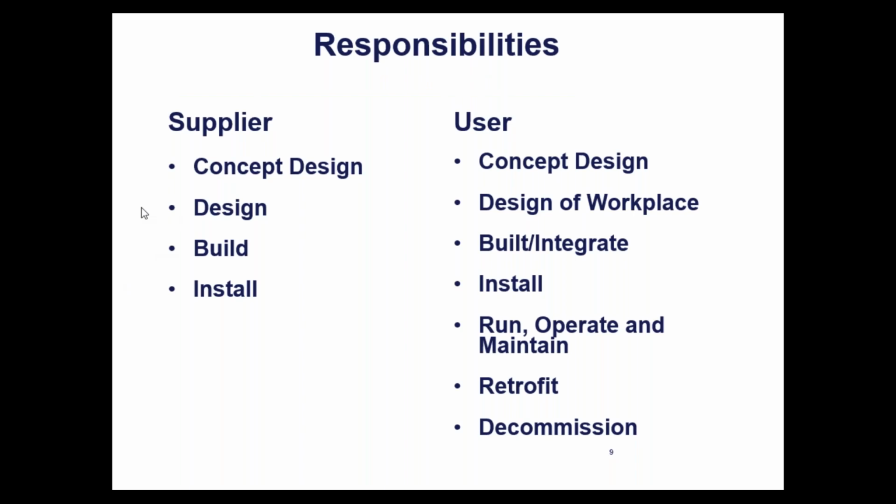For example, when you're trying to define what equipment we're going to design, the concept, we need to do a preliminary risk assessment. Then when we design the equipment and have it in a drawing, on a piece of paper, we ask, what are the risks associated with this equipment that we are building or designing? Then when you build the equipment, you need to perform another risk assessment, and your final one, normally from the supplier side, is when you're installing and debugging this equipment. Do we have the right interlocks? Do we have the protective fences? Do we have the right gates? Are the gates open from the outside only, or can you open them from the inside to escape in case of emergency? All that you need to take into consideration.